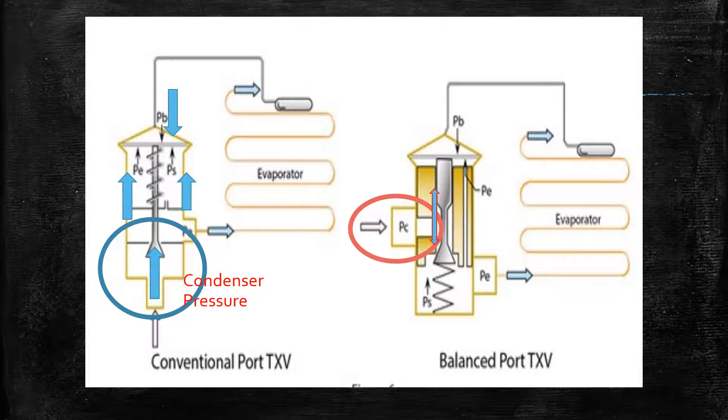Therefore, in a balanced port TXV the only pressures that we have acting upon it is the spring pressure, the evaporator pressure, and the bulb pressure, which gives us more accurate metering of the refrigerant into the evaporator.